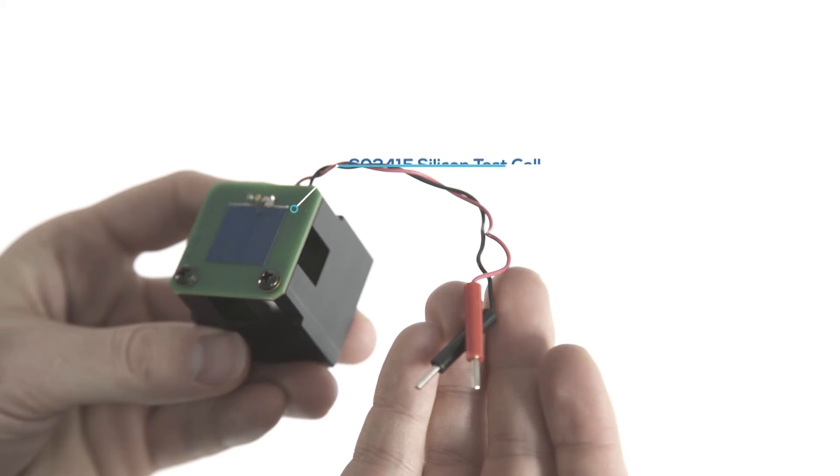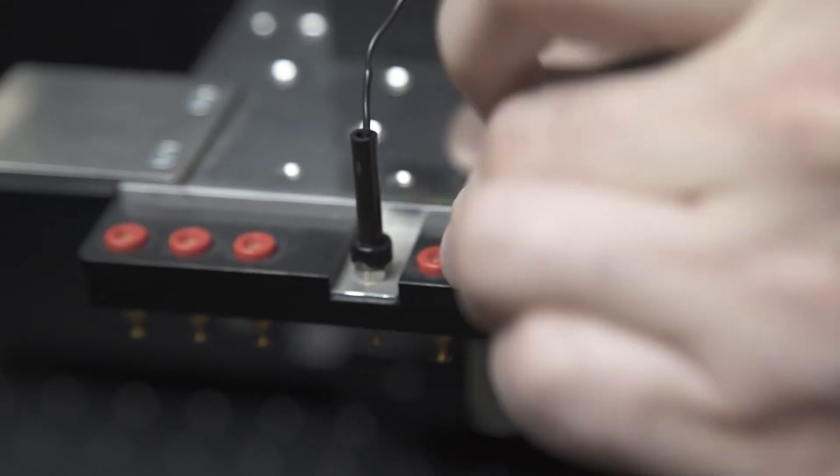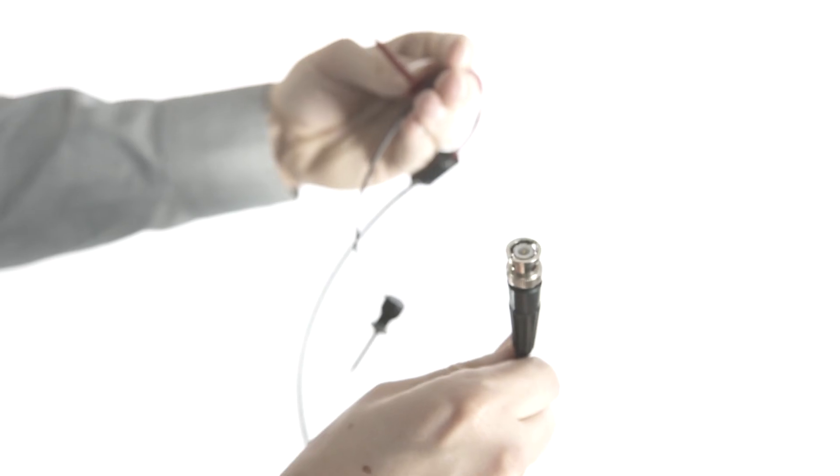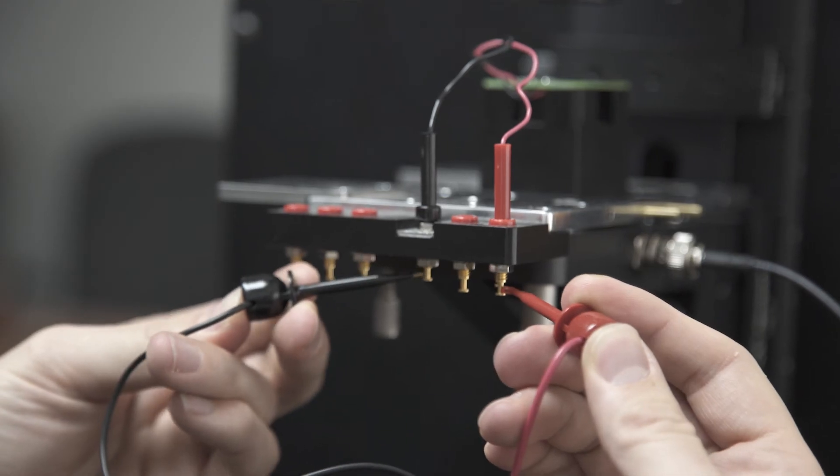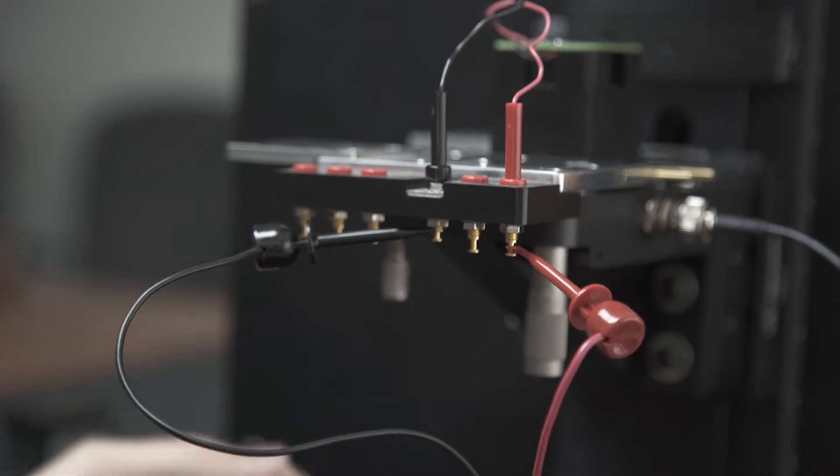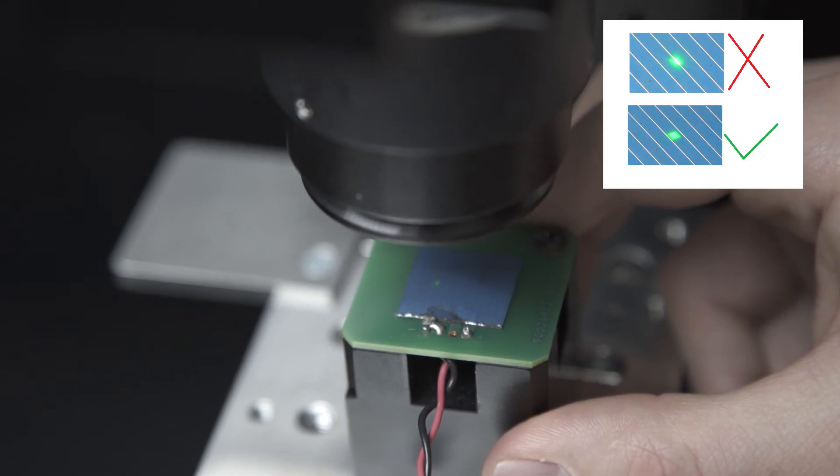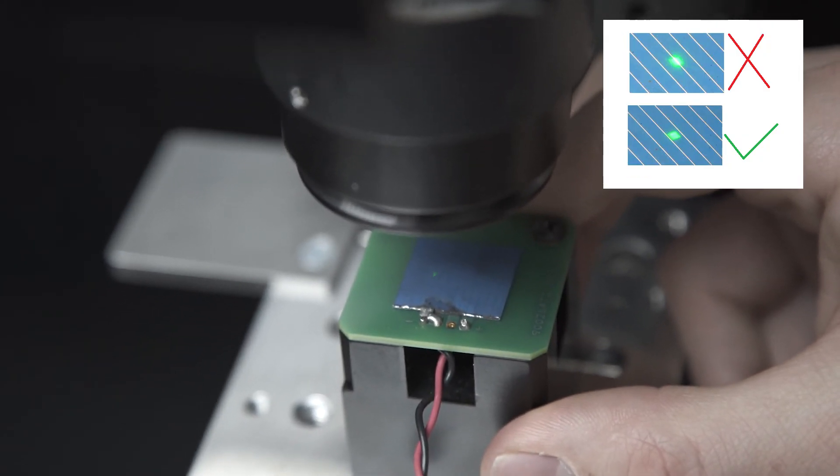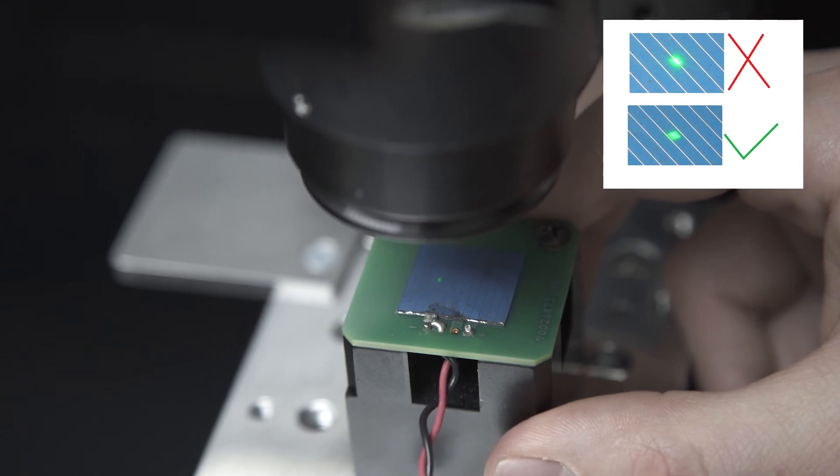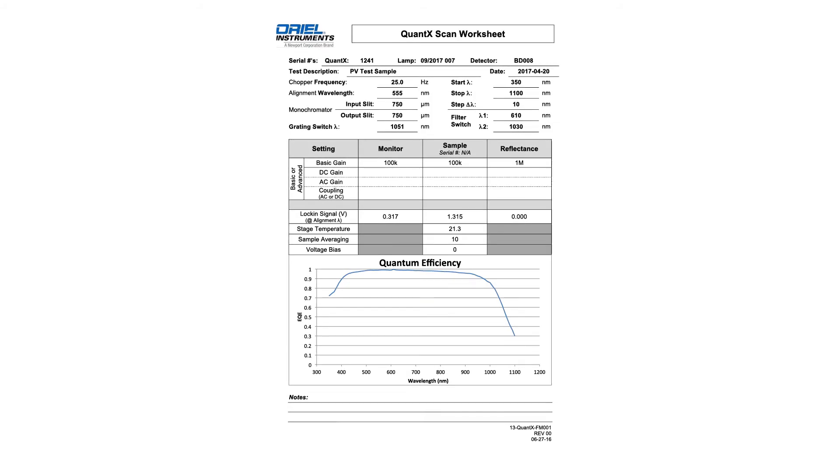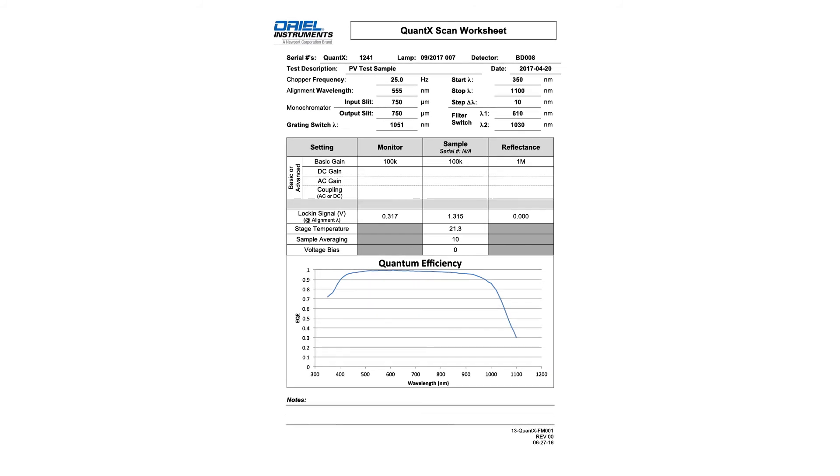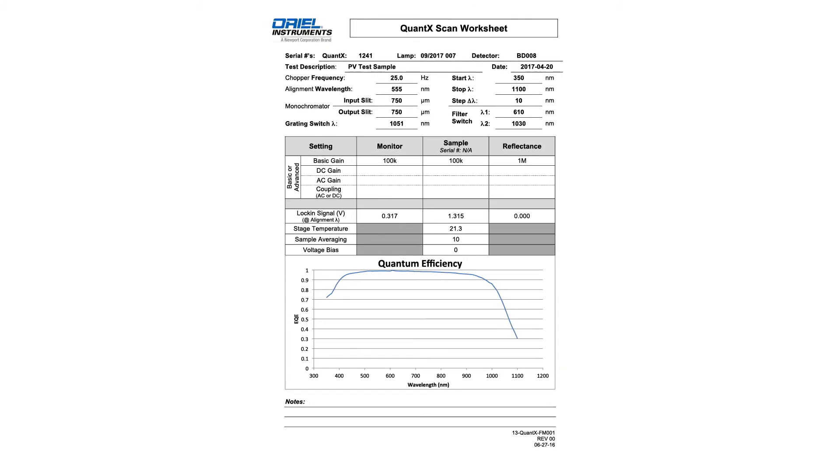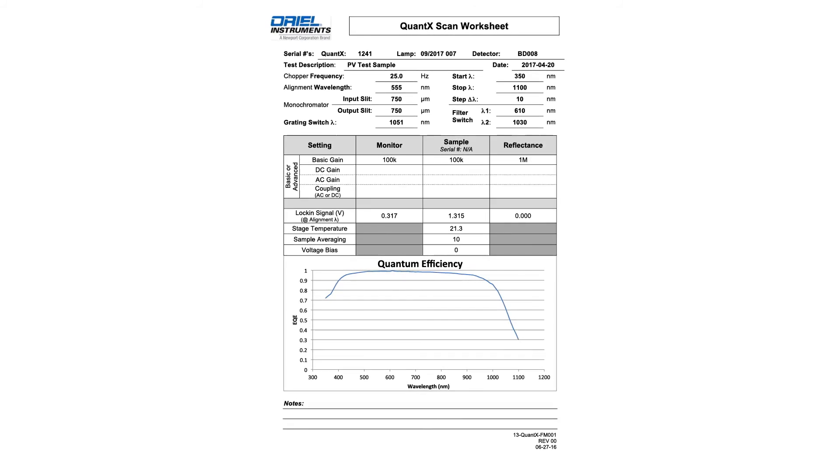This is the silicon test cell used to verify the system calibration. Connect the red and black pins into the jacks on the stage, then use the BNC to mini grabber cable to complete the circuit. Align the output beam in between the metal bus bars, avoiding direct illumination. A final test of this sample has been performed by the factory and provided on the USB drive. This can be used to compare results.